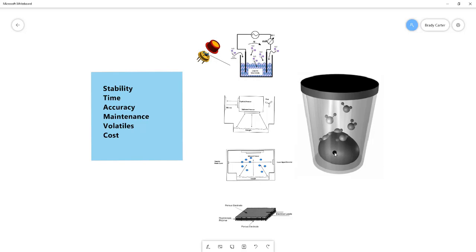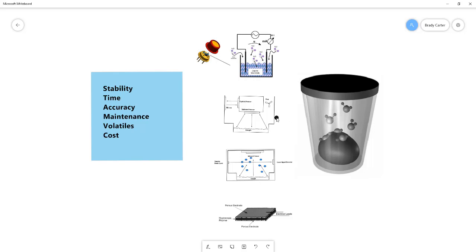But let's say that all those things are the same. So the stability settings, temperature, everything's the same, the electric property sensors will always be a bit slower than the other two methods because they need or require a step where the sensor itself comes to equilibrium with the chamber. And that can only happen after vapor equilibrium is achieved. So with all conditions the same, the chilled mirror and the TDL will be slightly faster than the other two methods.